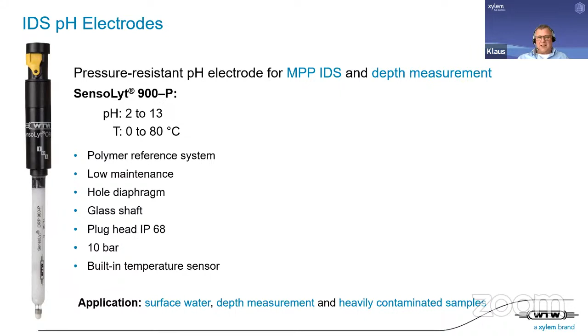Okay, this is a little bit special. Now we go to our most important laboratory electrode, and this is a really nice thing. This is the SenTix 980, which is a refillable electrode with a glass shaft and a so-called platinum wire diaphragm. The platinum wire diaphragm makes it very easy for the electrolyte to flow into the solution. And that means that they have an excellent contact.